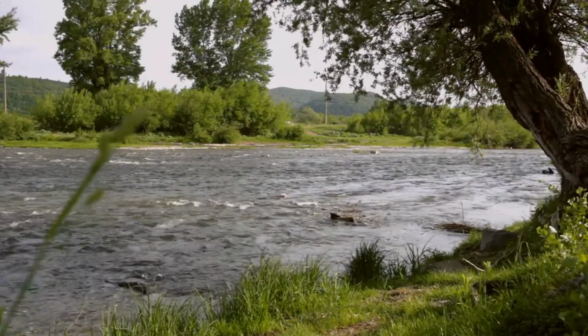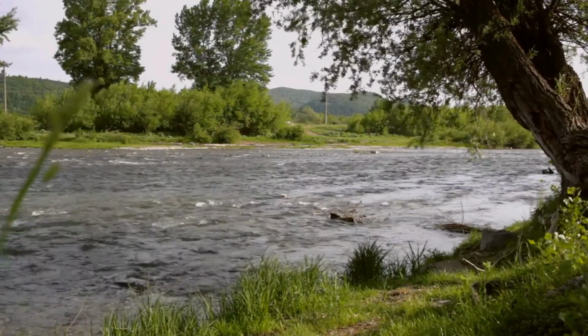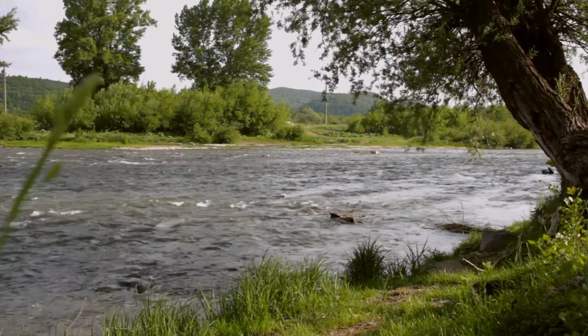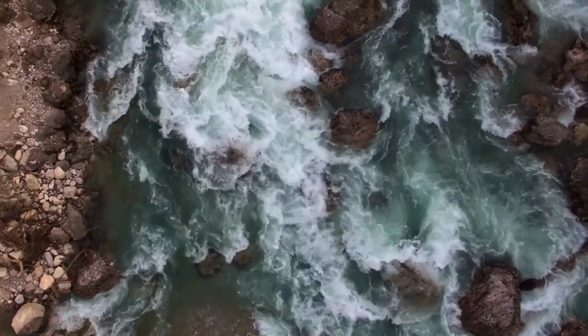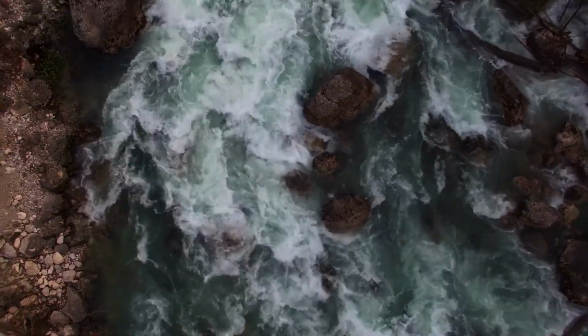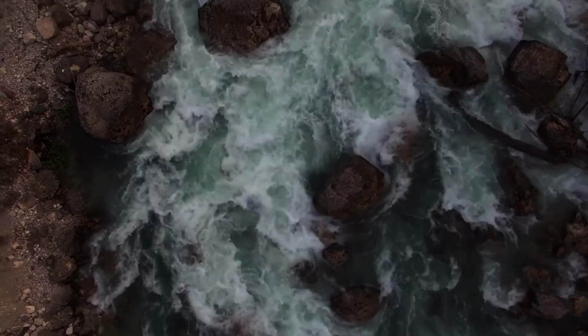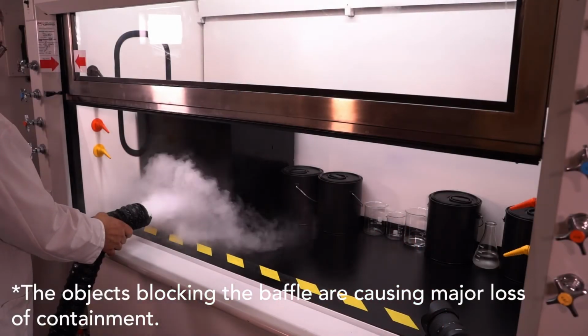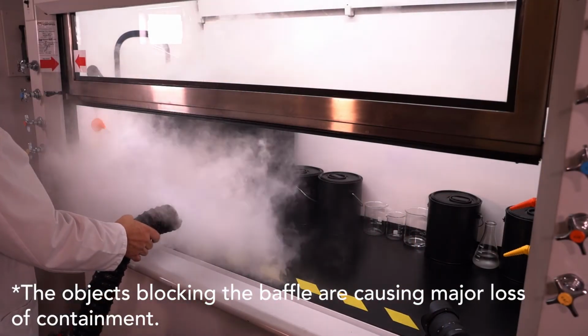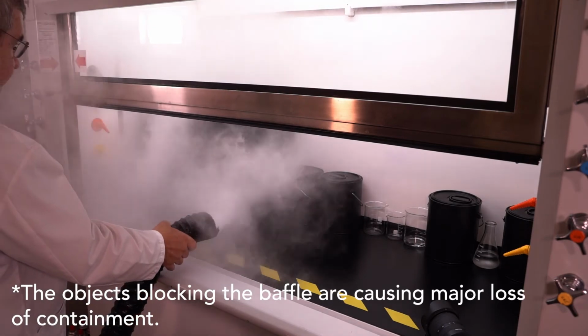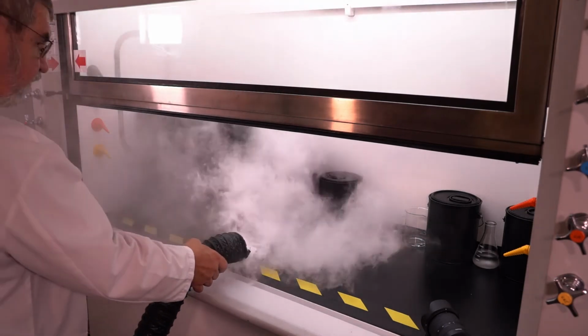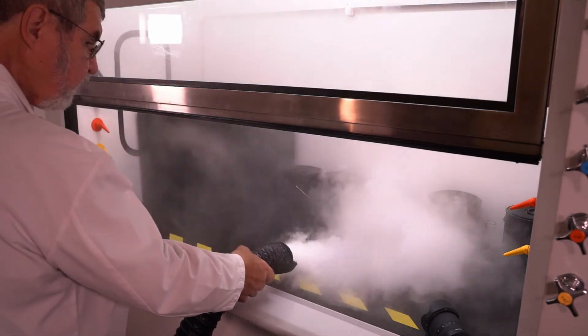Think of air as if it were water flowing down a river, smooth and calm. Now put some boulders in the river and the smooth flowing water turns into rapids. Objects in the hood do exactly the same thing to the airflow. These objects can create enough turbulence to cause the hood to lose containment, which could contaminate the lab air and create hazards for the users, the equipment, and the work.